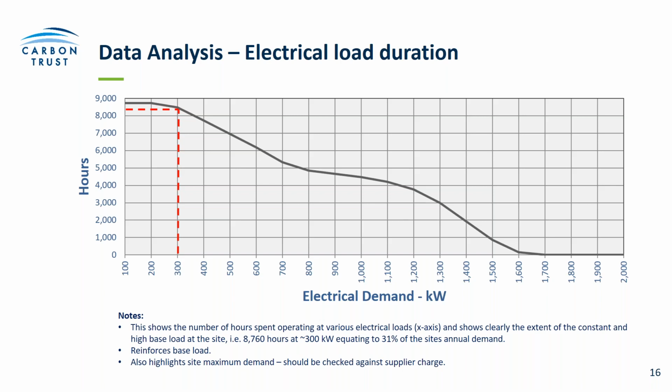If you're not coming anywhere near that, then you can have that reduced, and there's a good saving to be had from that. You need to be sure that you're not going to need that demand in the future, because if you have to go back and ask for it, then they will charge you to increase it again.